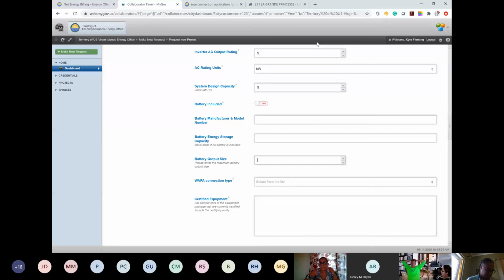Hi, thank you once again for the question about battery output size. Kilowatt capacity of a battery can be huge, but it's an irrelevant number. The battery is only going to put out what the inverter is demanding from it, and the inverter is not going to put out more than its kilowatt capacity, except now and then in very short surges.